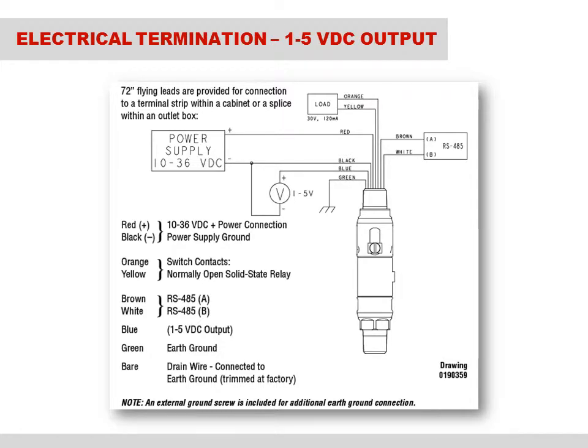This is the wiring diagram for the 1 to 5 volt DC low power mode of operation. This output is ideally suited for remote applications such as oil and gas well sites where instruments are operated with battery power. Note that the blue insulated conductor is required for a 1 to 5 volt DC output, and if needed, the HART communication protocol is also superimposed on the blue wire. Note that the red and black wires are also required to power the 815 PT instrument.